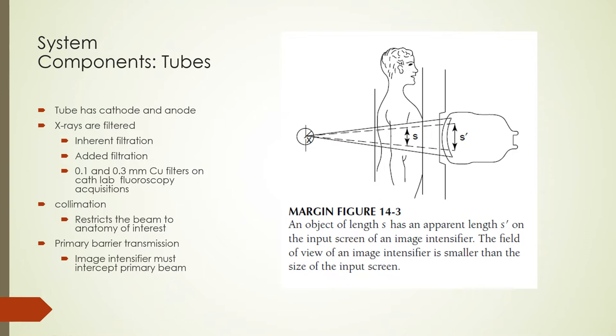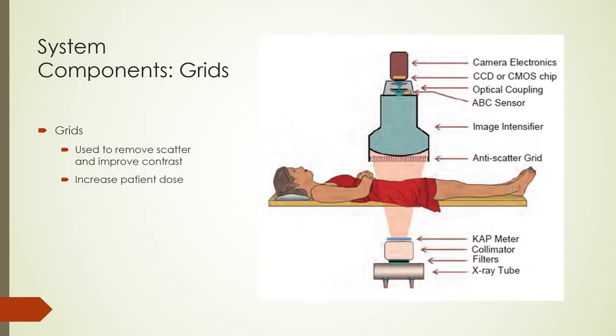Because fluoroscopy machines are made with the image receptor and x-ray tube mounted on the same support, they are aligned with each other. Image receptors must intercept the primary beam, which is checked by measuring the primary barrier transmission rate — done by placing a handheld x-ray detector behind the primary barrier while the fluoroscope is in operation. You can see that the primary beam is larger than the displayed field of view but still within the image intensifier input surface. On the image receptor side, a grid is used to remove scatter x-rays produced by the patient and to improve contrast. The presence of a grid increases patient dose.